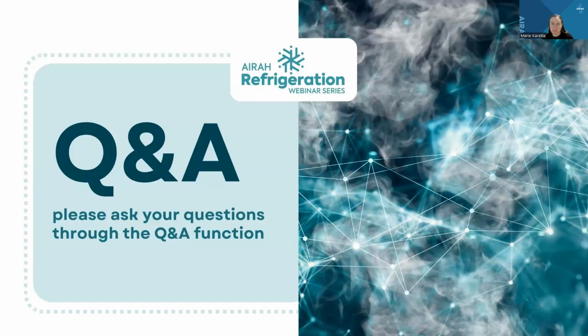How can we increase the defrost system efficiency? As I said, that formula came from the publication from the Massey University, I think, and I think it's probably an arbitrary figure. And as I say, it's a load estimation, so it will vary. I think often it's just judgment more than anything else, and every room's application is different. So I think we just have to do a judgment in terms of that fraction. But the formula is only a guide.